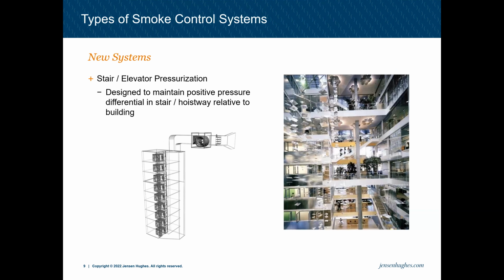So for the next couple of sections, we're going to start talking about the different types of smoke control systems, and we'll start with what's currently required, or the newer system. If we're in a newer building, our first item is stair and elevator pressurization. So what is it? Basically, we take a giant fan, usually on the top of a roof, that will take air and inject it into a shaft, a stair shaft or an elevator shaft.